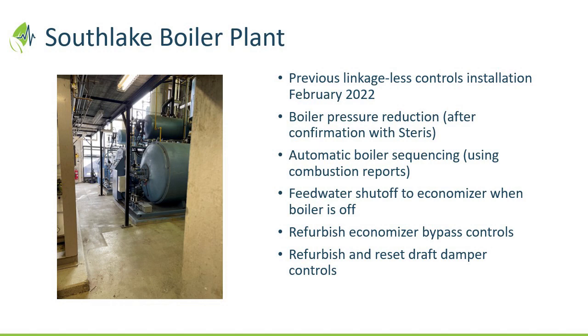So these other things here. The plant operator was already playing around with reducing the steam pressure. Steam pressure improves the efficiency of the boiler. So now thinking about putting that in place, but not just the operator turning it down and hoping nothing goes wrong, but it's the conversation. It's everybody together in the boiler room talking about how to do it, what it would look like, who to check with. So the Steris decision, let's talk to the sterilizer folks first to make sure they're okay with that. But bringing down the steam pressure improves efficiency.